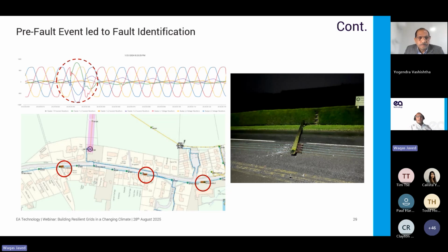The event was flagged as a credible pre-fault, and the location algorithm triangulated three possible sites along the feeder, all associated with bare conductor spans. A few days later, a field crew confirmed that two poles had snapped and grounded just outside the spotted areas. If you see, the pole has been snapped on the right hand side of the figure. Fortunately, the issue was already under repair by the time inspections occurred.